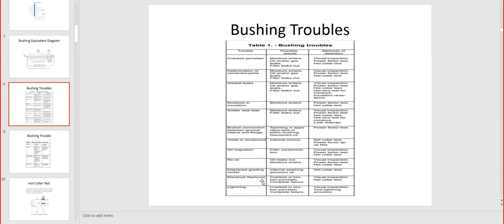Electrical flashover: bushings are also outside, so remember they are exposed to all the natural factors. I was in an inspection in Ottawa, and they had a 125 megawatt transformer failure because, they don't know exactly what it was, probably a raccoon that walked over the transformer, got zapped, and all it left from the raccoon was thousands of needles that penetrate, becoming incandescent, and penetrate the actual bushing, the porcelain. So they had to replace that bushing, because even cleaning is not going to give you the surface of the bushing that needs to be perfect, like porcelain, and no asperity, no chips, no cracks, no nothing. So it needs to be perfectly clean and shiny.